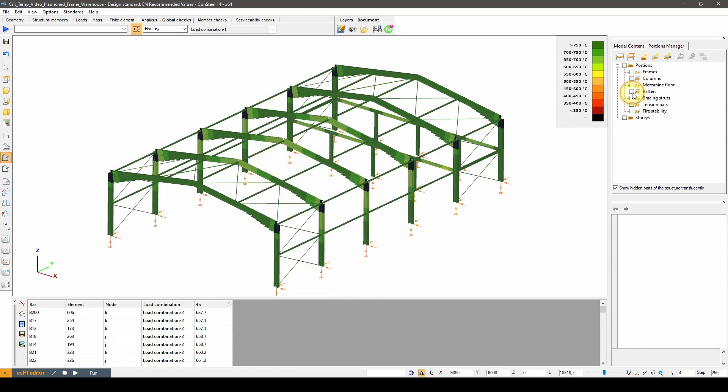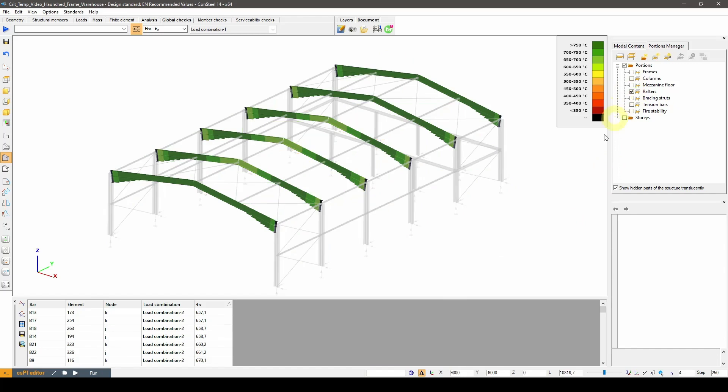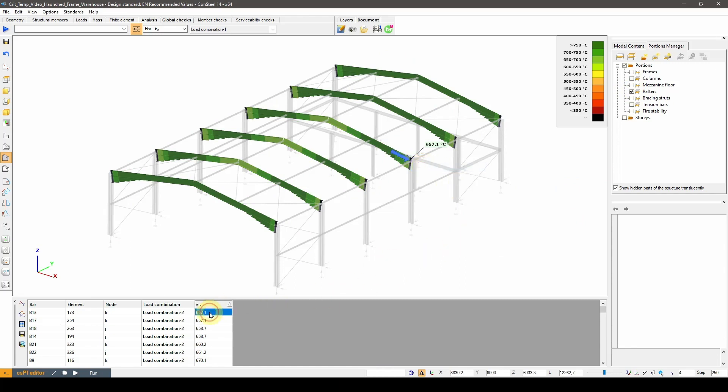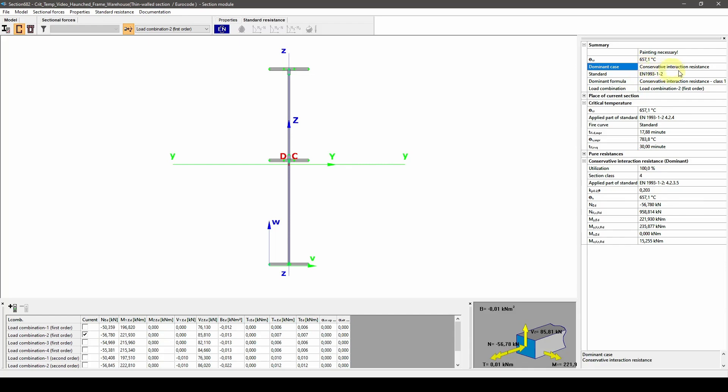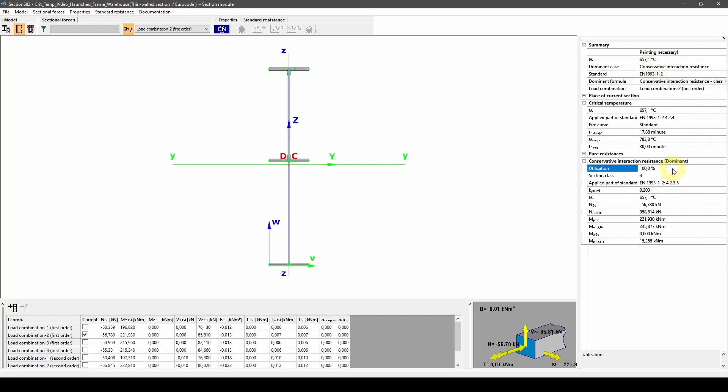Now we can see the critical temperature results for all of the members. If we switch to the rafters portion, we will have the lowest critical temperature on the top of the results table for this portion only. Let's give it a marker and check it out in the section module. As we can see, the main result is the critical temperature. We can also see that the dominant calculation method was the conservative interaction resistance in this case. We calculated the material temperature where this method gives 100% utilization, which by definition is the critical temperature. That's why those two values are equal.